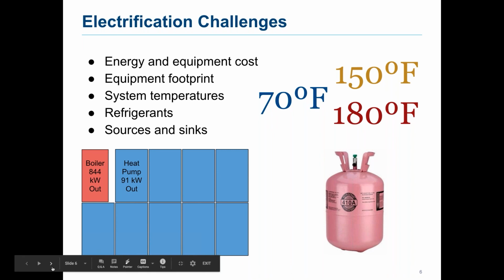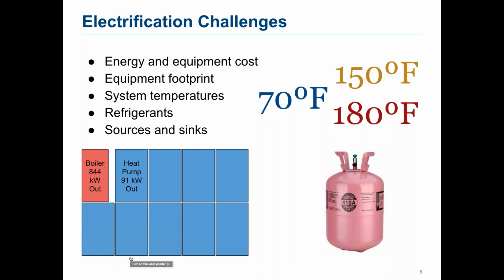Another challenge we're running into is equipment footprint. A boiler is a relatively simple piece of equipment. Heat pumps use a refrigeration cycle, so they have a compressor and two heat exchangers. As an illustration, comparing equipment we currently have on site—an existing condensing boiler and an existing heat pump in one of our new buildings—shows what it would take to convert one of these boilers to a heat pump: the footprint is about 9 or 10 times greater. In a retrofit application, that's a big issue we have to address, in particular by increasing the efficiency of our system so we don't need as high a peak load.